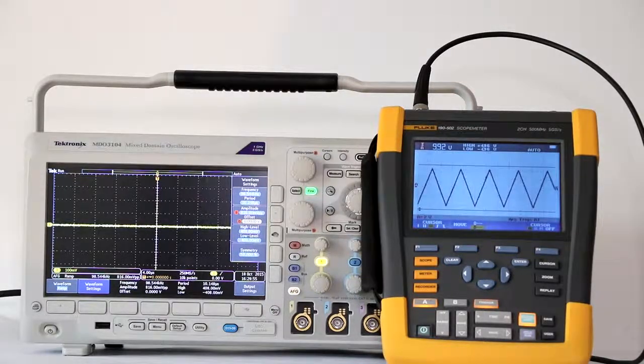F4 highlights the third menu item. F3 scrolls throughout it. 1/T, the reciprocal of time, is highlighted. The frequency in hertz, in this case, kilohertz, is now shown in the cursor readout. This is a very useful feature, since frequency would be difficult to estimate by counting divisions and ticks on the screen. The fourth menu item simply toggles cursors on and off. The whole thing is quite simple once you become familiar with the F1 through F4 buttons.